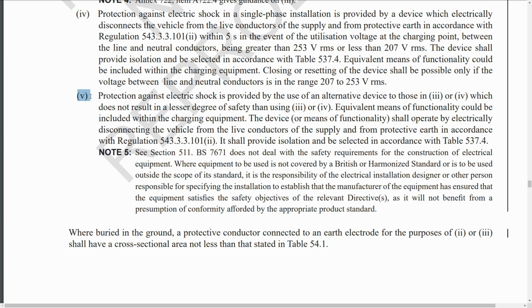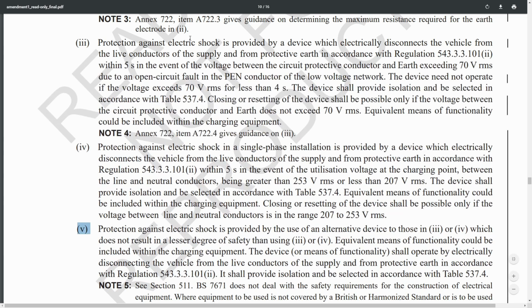Now, number 5 here, which is by far the most vague item of this, says protection against electric shock is provided by use of an alternative device to those in 3 or 4, and that's the one we were just talking about there, which does not result in a lesser degree of safety than using 3 or 4. Equivalent means of functionality could be included in the equipment, and it shall operate by doing the same thing, disconnecting all those conductors and the protective earth, and it shall provide isolation and so on. So essentially this is some sort of cover-all situation for stuff that may not exist yet, and may not be specifically mentioned here. And essentially it's covering the 2 items we had earlier, so it's 3 and 4, the unicorn device, which nobody makes, and then this other device which monitors the voltage between the conductors, which is a thing you can currently buy.